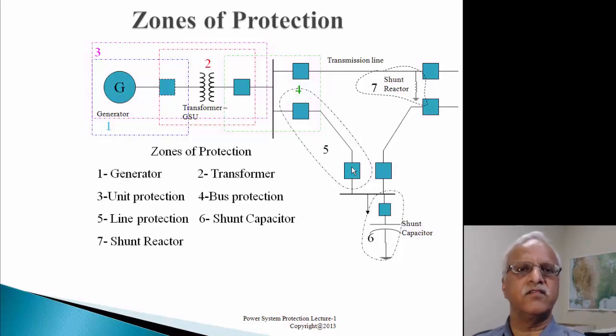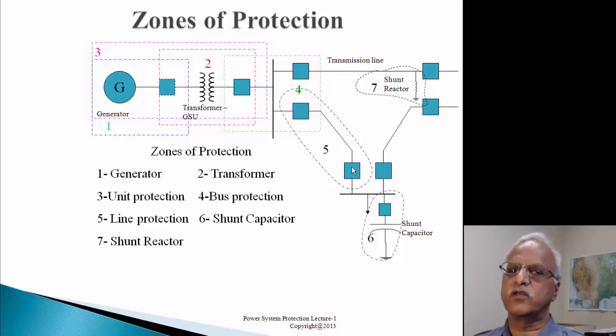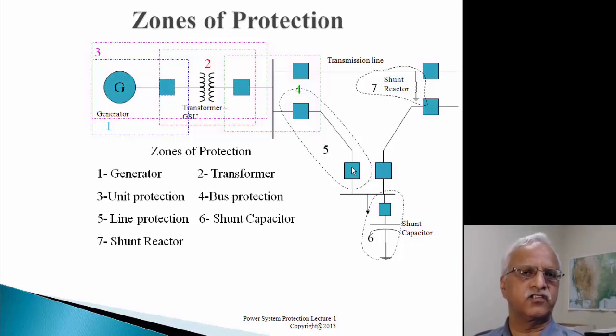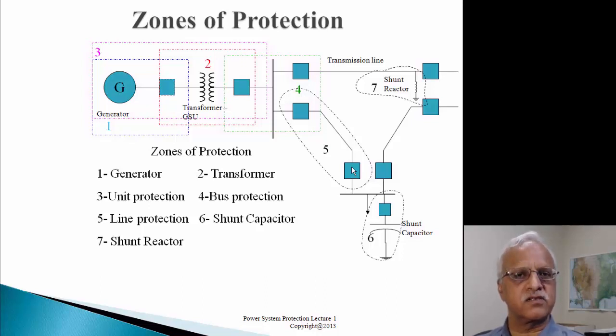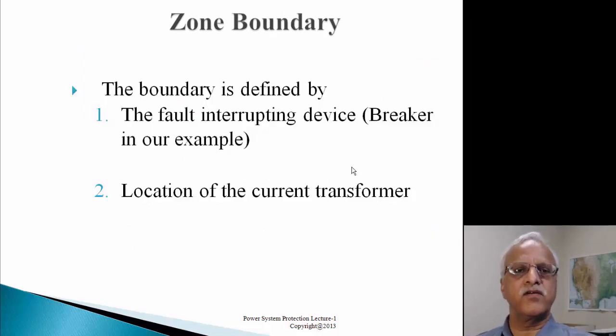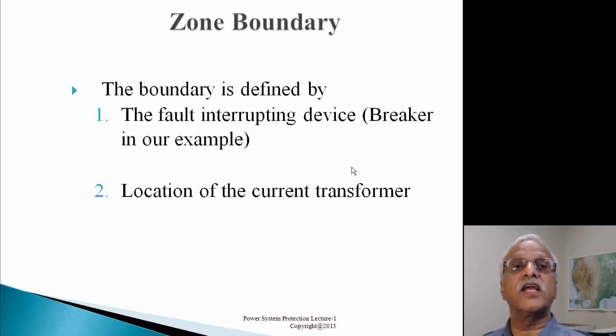We have defined zones of protection. The generator zone of protection opens only the breaker associated with the generator. The transformer zone covers the transformer and opens breakers on both high side and low side for a fault or abnormality. Unit protection opens on the high side; line protection opens breakers on both ends. The intent is to detect the fault and isolate only the faulted equipment. A zone boundary is defined by the fault interrupting device - the breaker - and the monitoring device, the location of the current transformer.